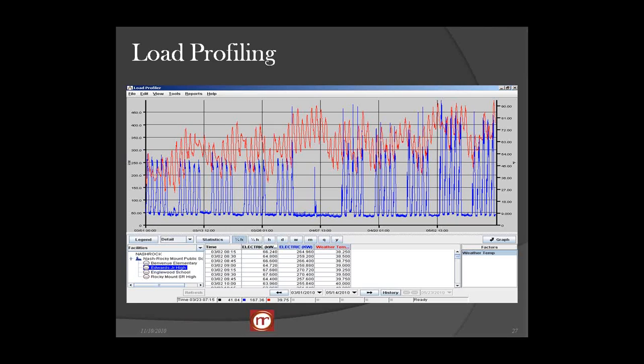Got 2 chillers, and I want both running at the same time. That's what we're currently studying, and then we may change the logic and see if we run both on staggered intervals, will it unload and reduce the KW. Right now, it looks to be run one, bring the second one on if needed. And also, there's a second clue here to what's going on.